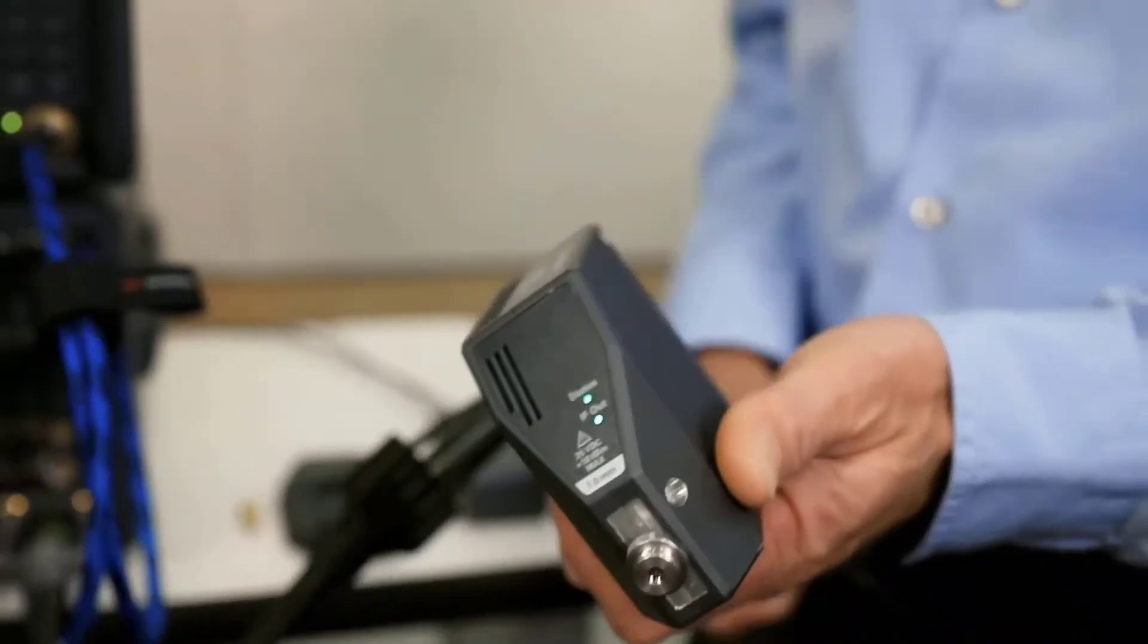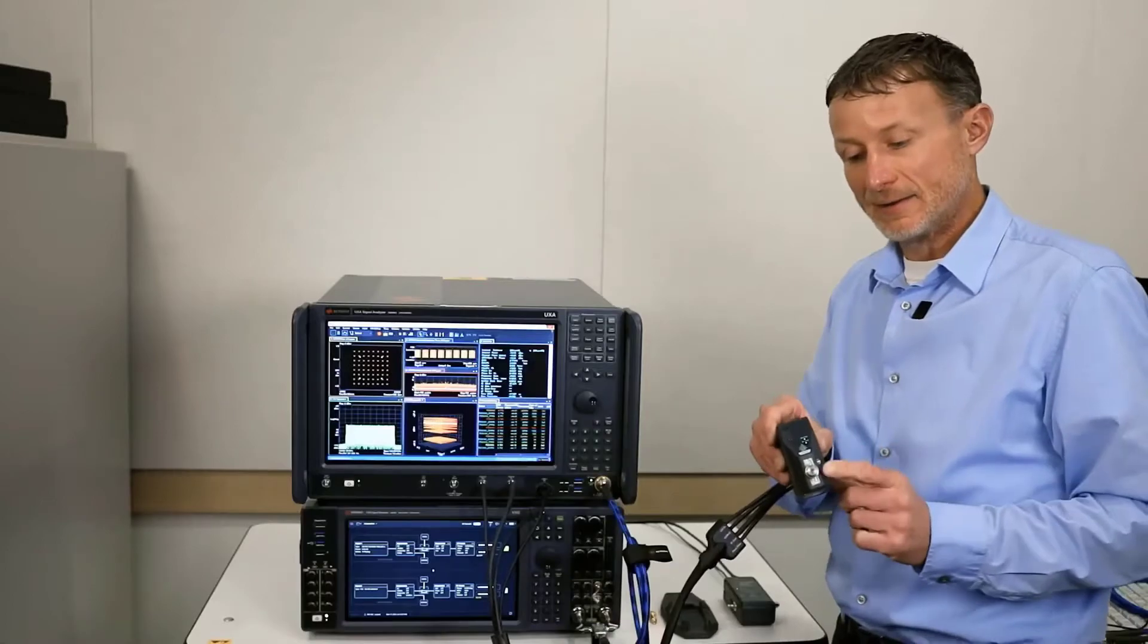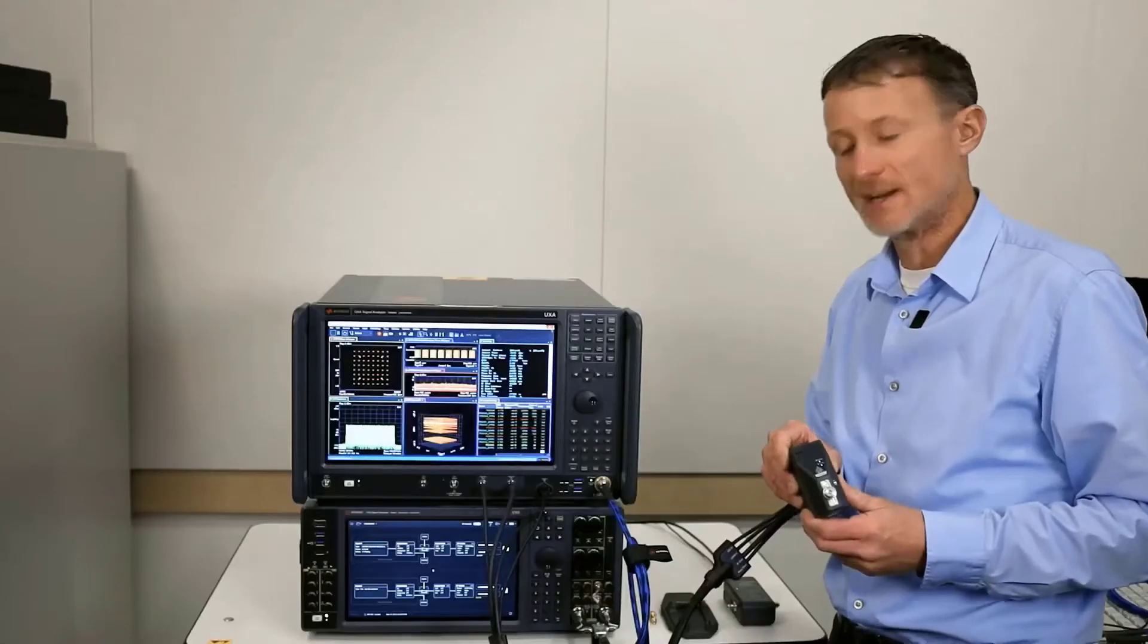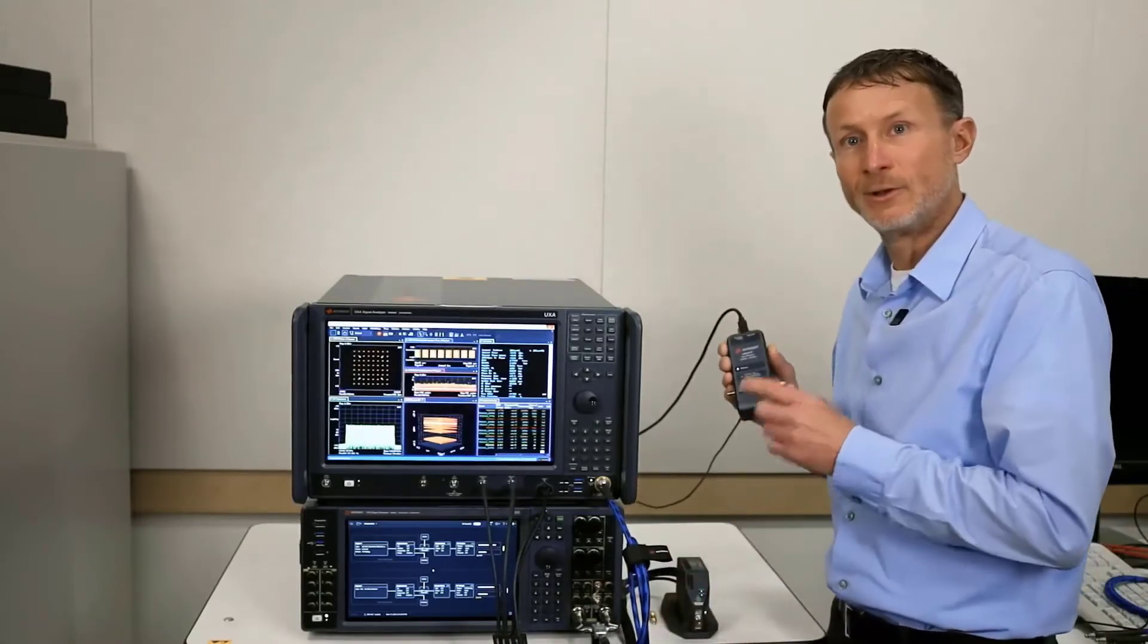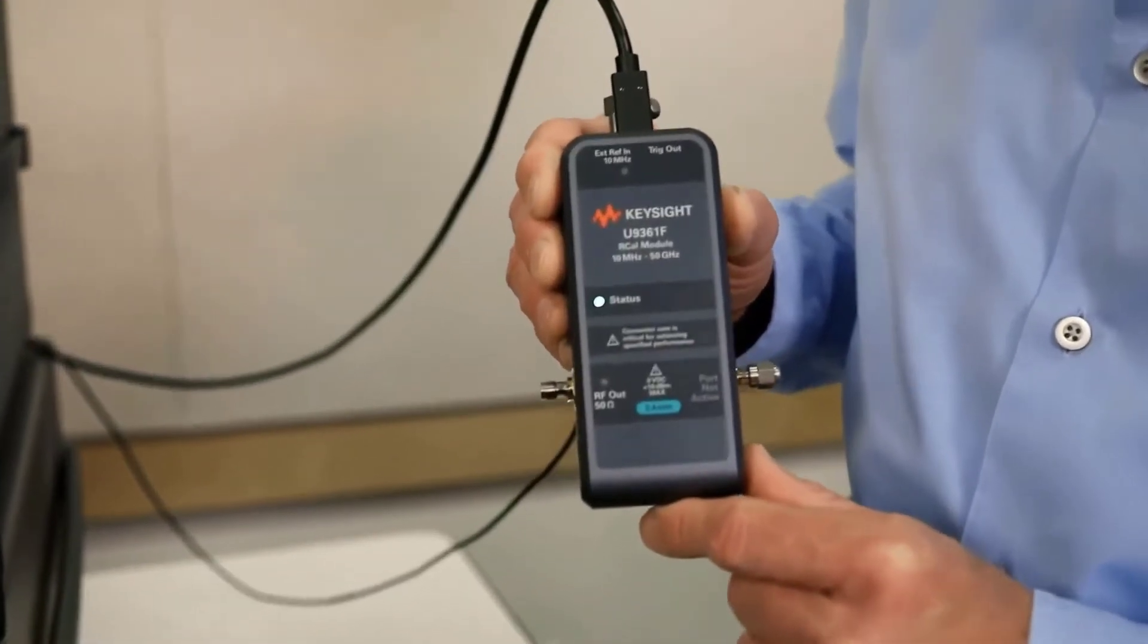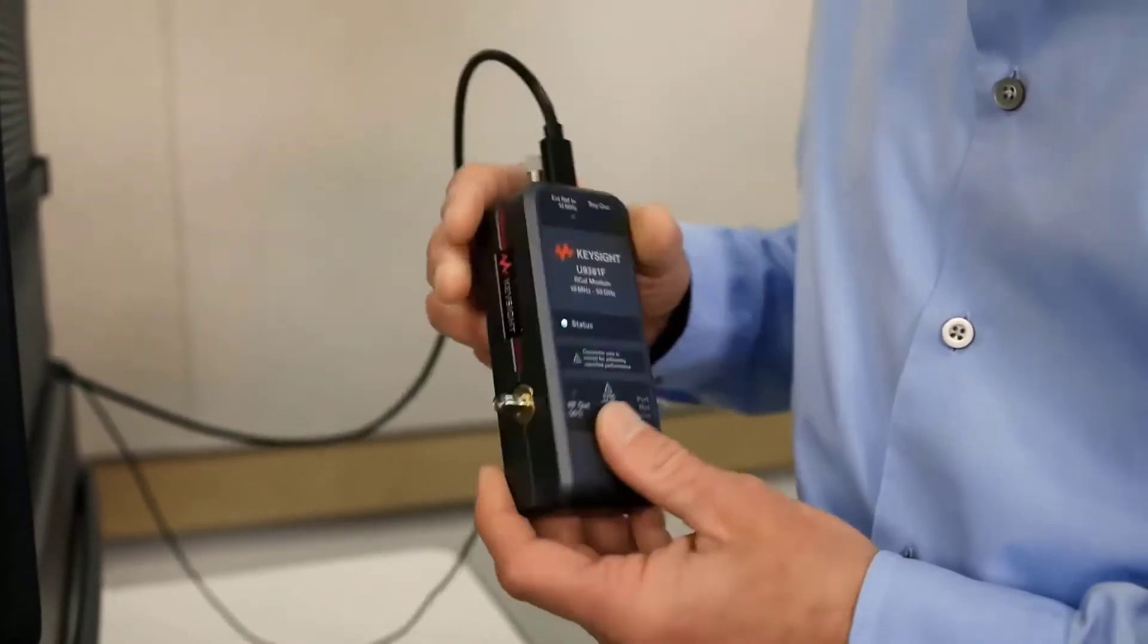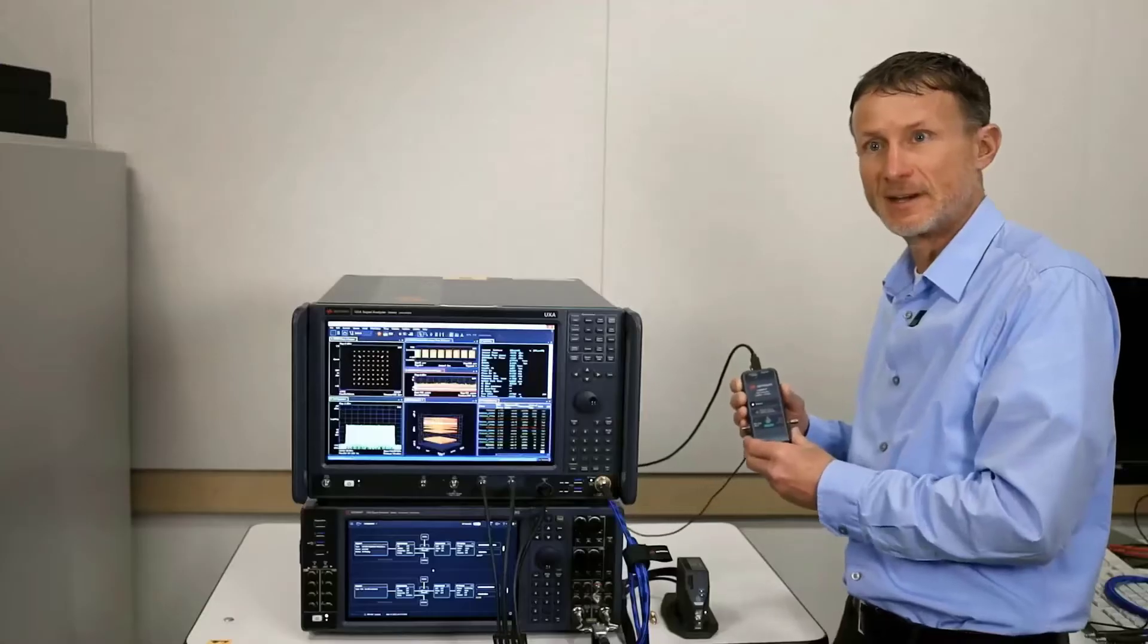It's portable, small, and compact. You can position it right at the device under test, and this connector allows you to measure basically from DC all the way to 110 gigahertz. Lastly, we have a new R-Cal module, which also goes to 110 gigahertz and allows you to recalibrate from the front panel of the instrument or the remote head right to your device under test.